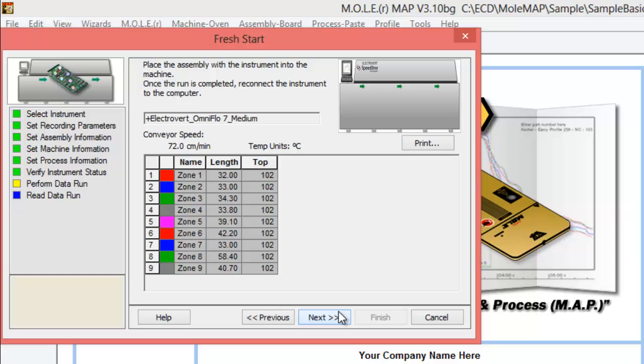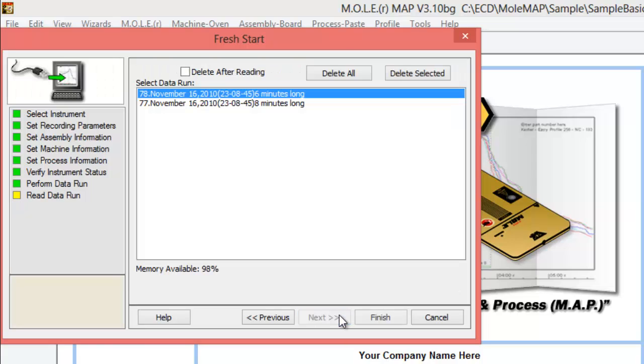We can go ahead and click next. That's going to send the programming through to the profiler. If you do want to follow this fresh start wizard all the way through to the end, it notes here to go ahead and disconnect the instrument and hook up your assembly to it and go run a profile. And once you've done that.